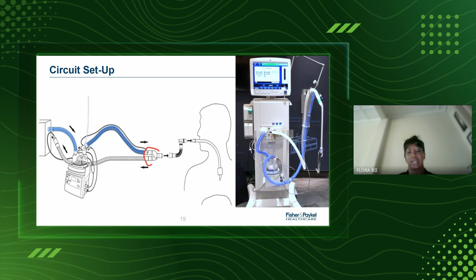But it's also important that I mention that because of differences in circuit technologies, it's highly possible as well to be able to heat the expiratory limb as well, so that condensate management is done optimally. So this is just a setup, an actual humidification setup to show you where each part falls in as far as humidification is concerned. For reusable circuits, there are differences from the one that I've just shown you earlier and what I'm showing you now.